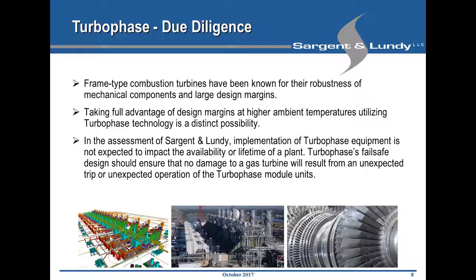And in our assessment, clearly the gas turbine is designed anyway for the larger mass flow at lower ambient temperatures, and therefore the additional mass flow that is being introduced, 5%, is really not changing the maintenance or operation of the power station. It does not increase. Obviously, you have a small additional maintenance due to the reciprocating engine that is used to drive the external compressor, but this is a fairly small unit, and thus it's not a big difference.